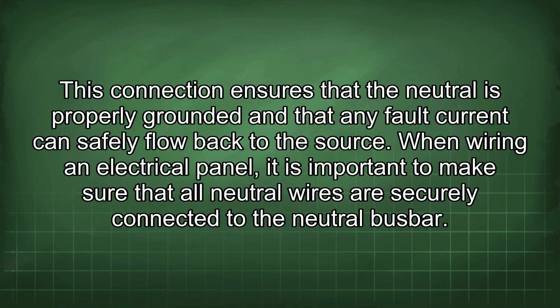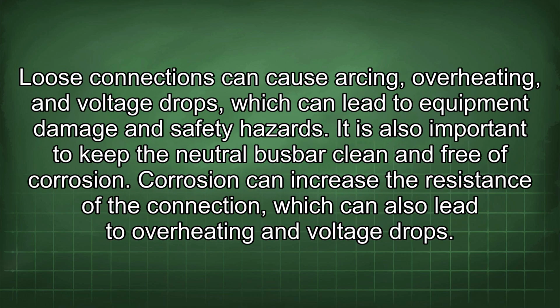This connection ensures that the neutral is properly grounded and that any fault current can safely flow back to the source. When wiring an electrical panel, it is important to make sure that all neutral wires are securely connected to the neutral busbar. Loose connections can cause arcing, overheating, and voltage drops, which can lead to equipment damage and safety hazards. It is also important to keep the neutral busbar clean and free of corrosion. Corrosion can increase the resistance of the connection, which can also lead to overheating and voltage drops.